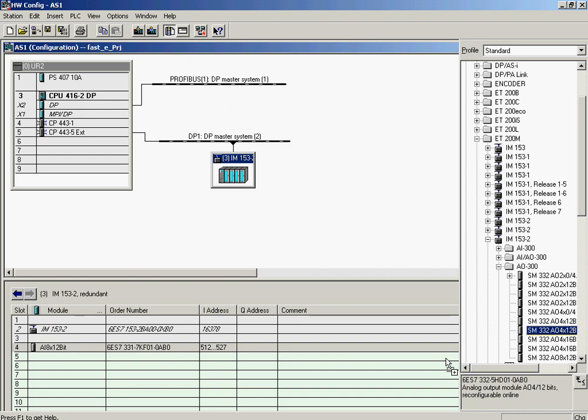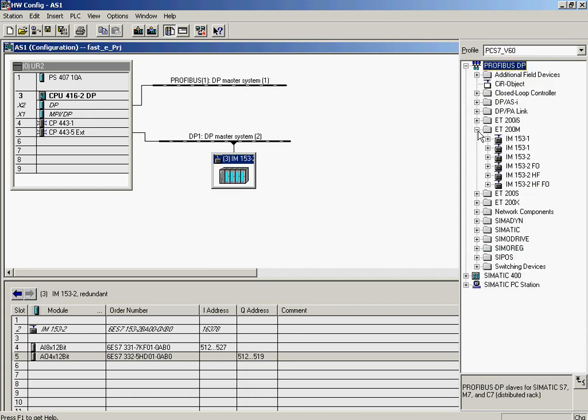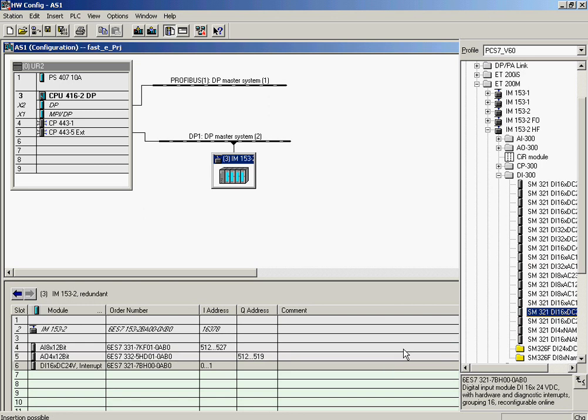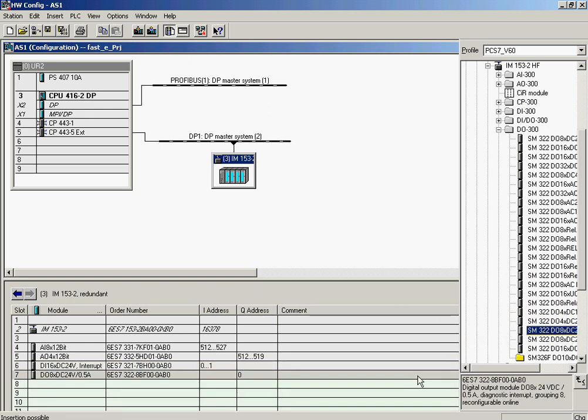However, we recommend working with the PCS7 V60 catalog, since it contains the subset of available hardware modules optimized for use with PCS7 V60, enabling you to work more efficiently. The digital input module from the PCS7 V60 catalog is plugged into slot 6. The last module to be configured is the digital output module in slot 7. The ET200M rack was expanded with analog and digital input-output modules based on the hardware to be used on the project.